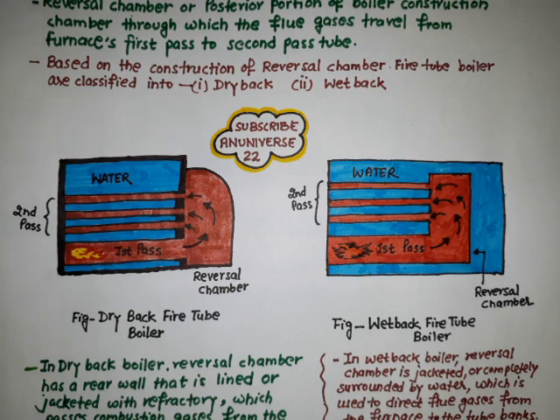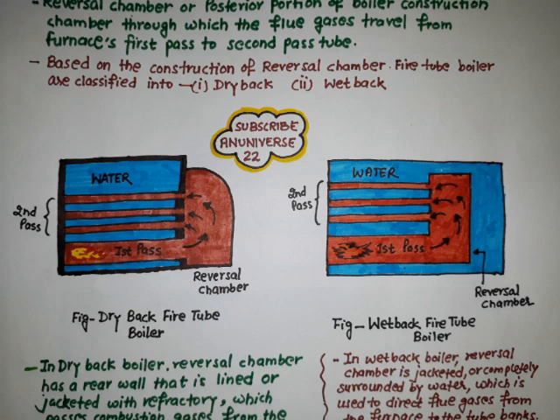The wet back boiler has separate tube seats between the tube passes and offers a more optimal functional footprint with a lift-off or split-hinged door that requires no cool-down period and can be opened immediately. There is no expensive refractory to maintain, and internal pressure vessel maintenance like cleaning is straightforward.